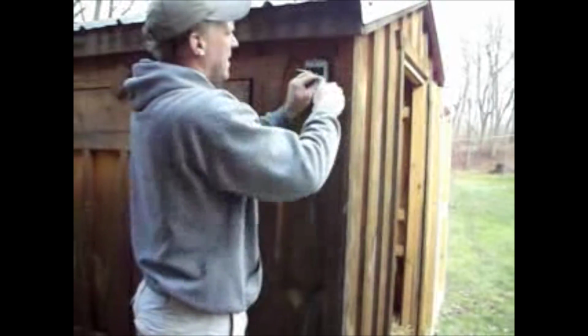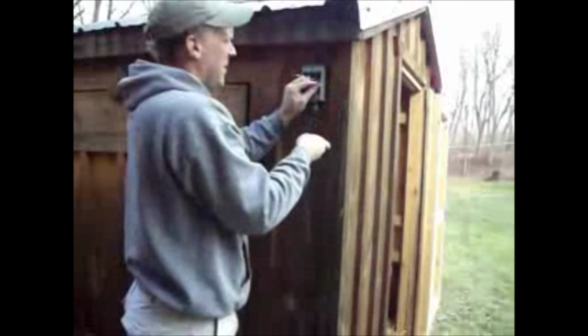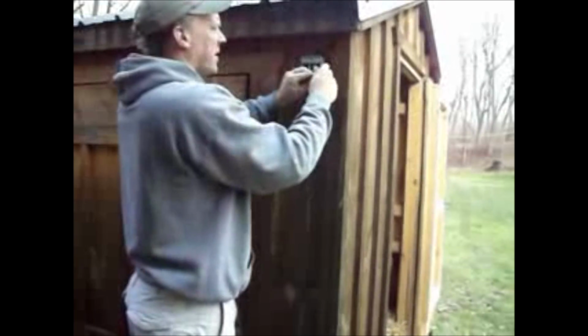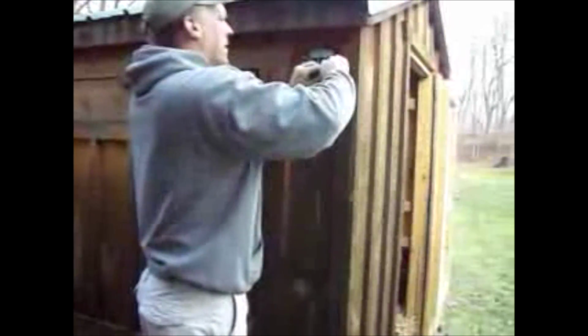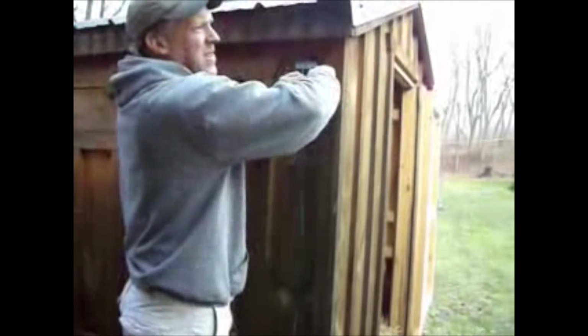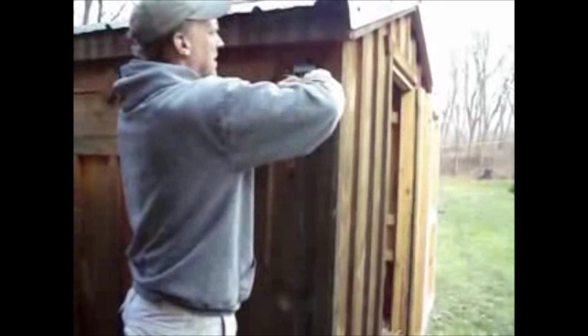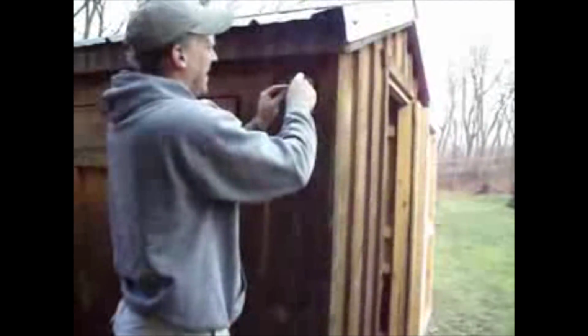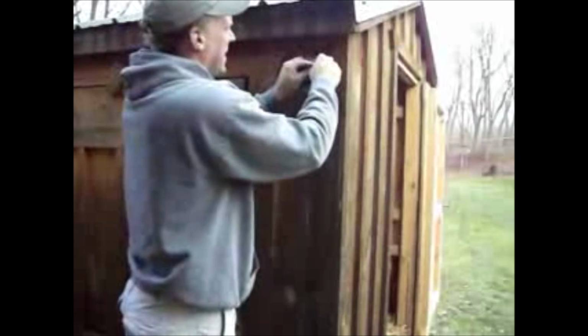Alright, next job is to connect the wires. We have the wires coming in from the inside, connecting here to the outside. With the ground, you'll have 3 wires to connect. You'll need a wire nut that can handle, that I actually included, that can handle 3 14-gauge wires. You attach those. There's green to the 2 coppers, so all the ground's together. The 2 whites get connected together.